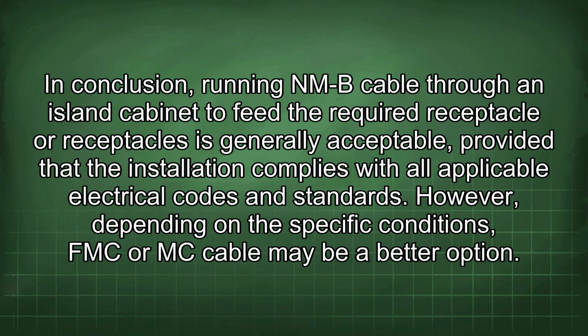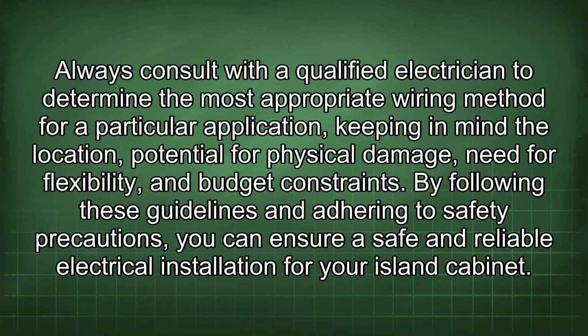In conclusion, running NMB cable through an island cabinet to feed the required receptacle or receptacles is generally acceptable, provided that the installation complies with all applicable electrical codes and standards. However, depending on the specific conditions, FMC or MC cable may be a better option. Always consult with a qualified electrician to determine the most appropriate wiring method for a particular application, keeping in mind the location, potential for physical damage, need for flexibility, and budget constraints. By following these guidelines and adhering to safety precautions, you can ensure a safe and reliable electrical installation for your island cabinet.